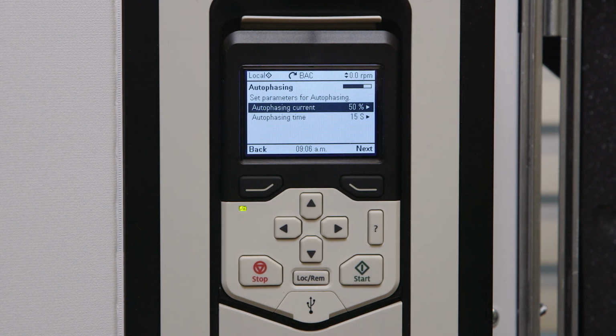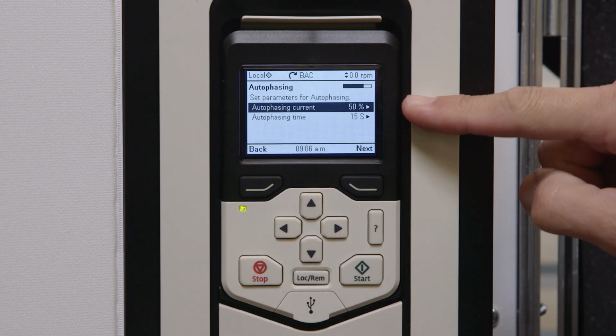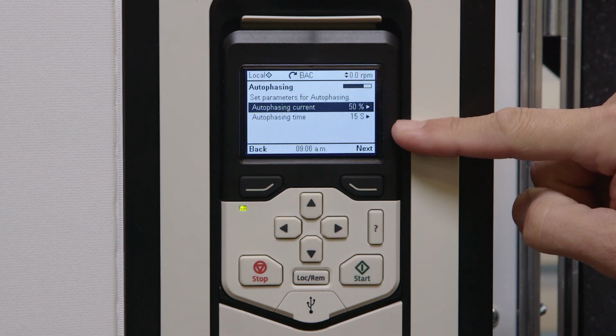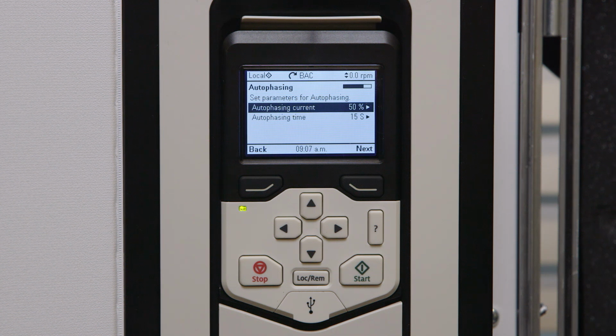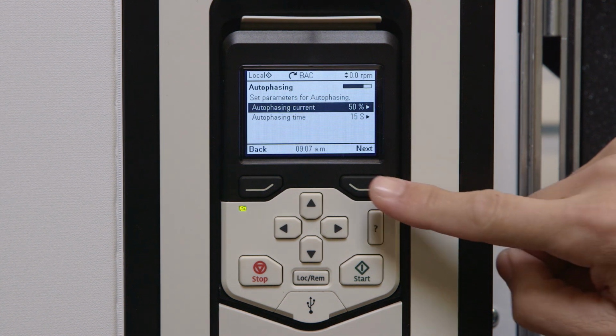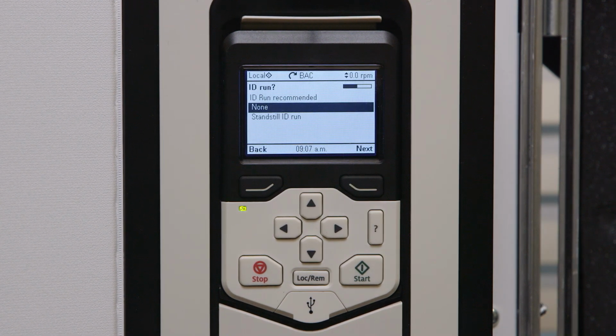Now, let's view the auto phasing. This is the automatic routine that lines up the motor magnets to the electrical motor poles. This happens on every start signal. Leave the default values at 50% and 15 seconds. These values can be adjusted later if you experience cogging. Press Next.